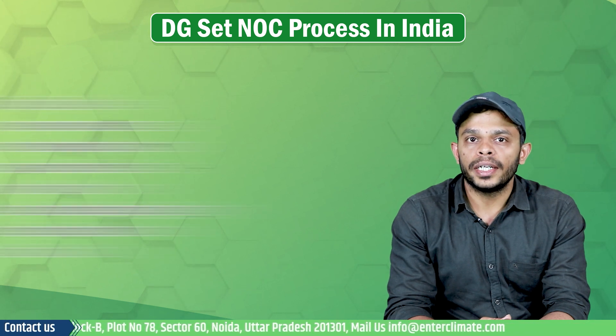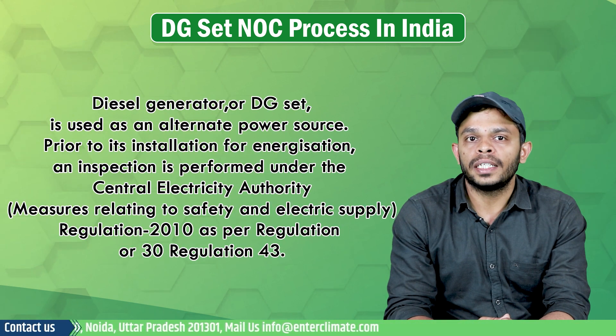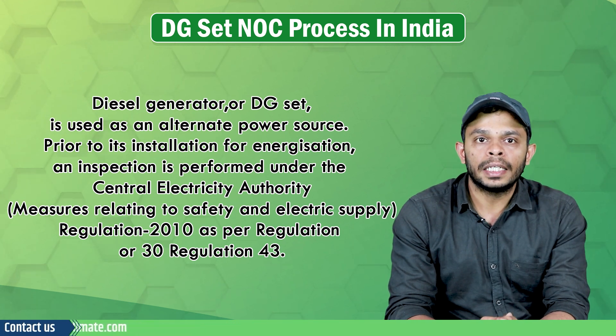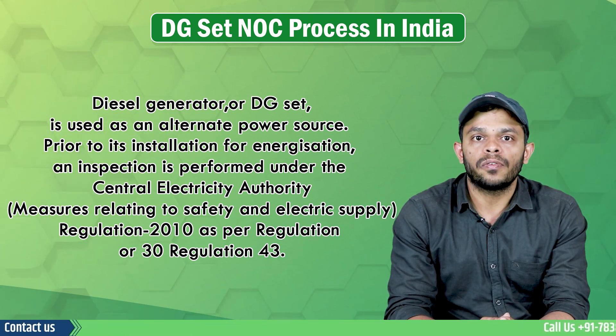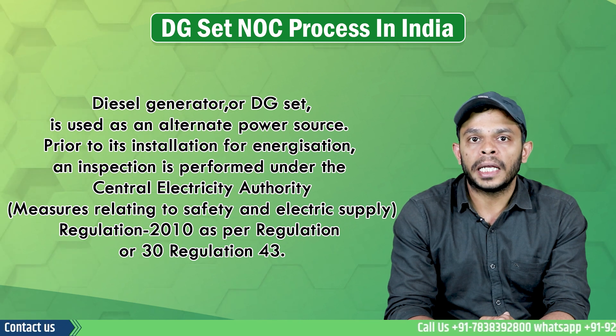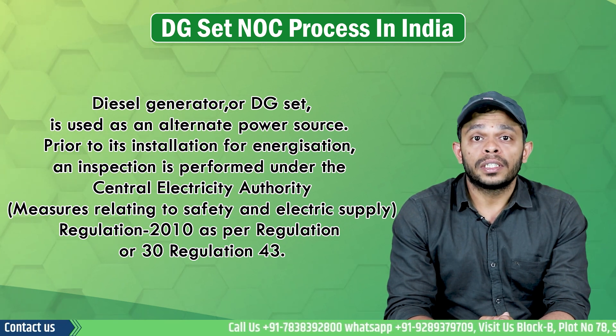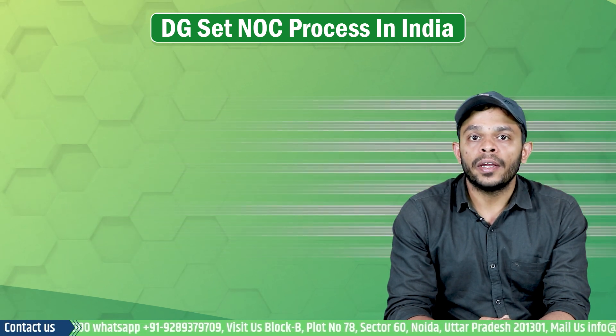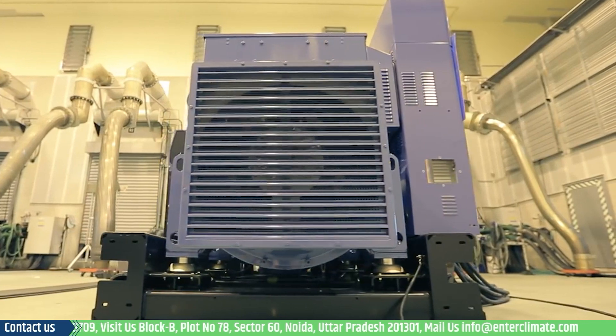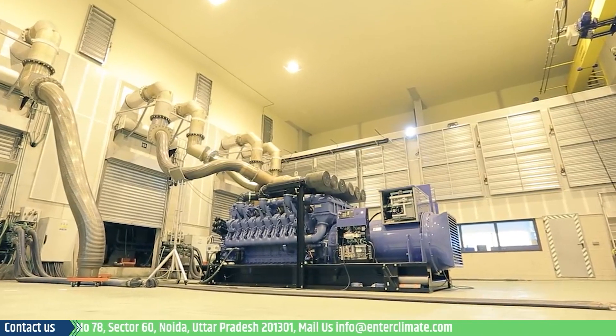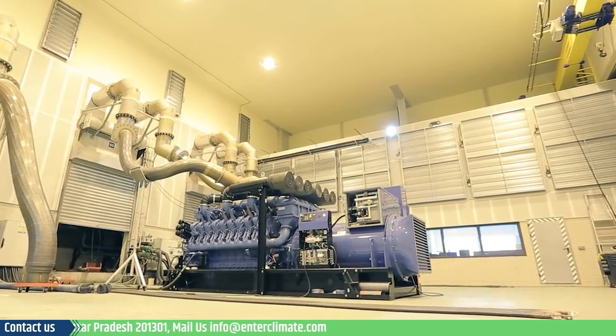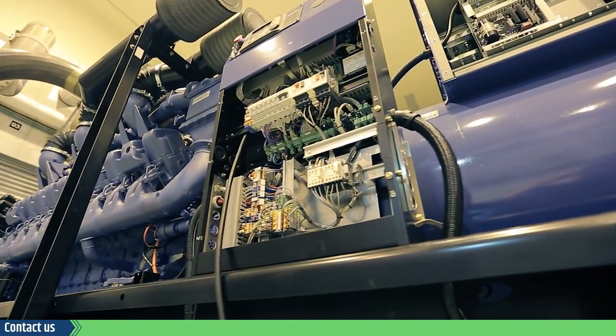A diesel generator or DG-SET is used as an alternate to a regular power source. Prior to its installation and energisation, an inspection is performed under the Central Electricity Authority Regulations of 2010 under Regulations 30 and 43. The applicant has to apply online to the department for this NOC in two stages: first for the approval of the generating SET plan, and thereafter to get the diesel generator inspected by submitting a work completion report.